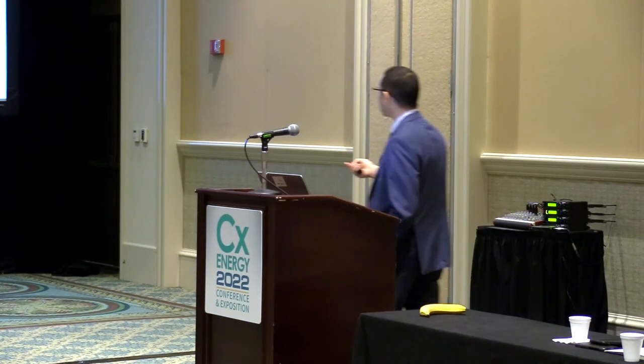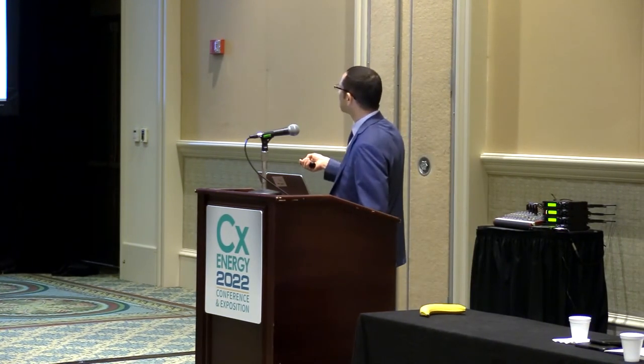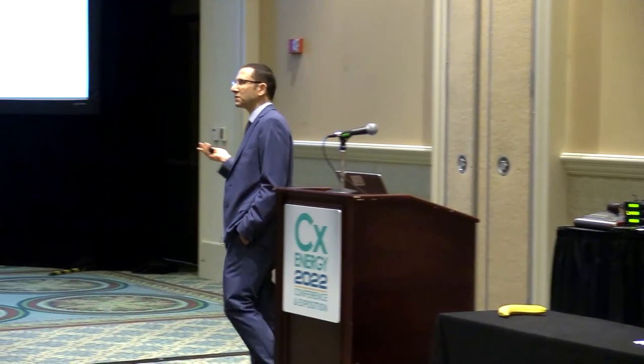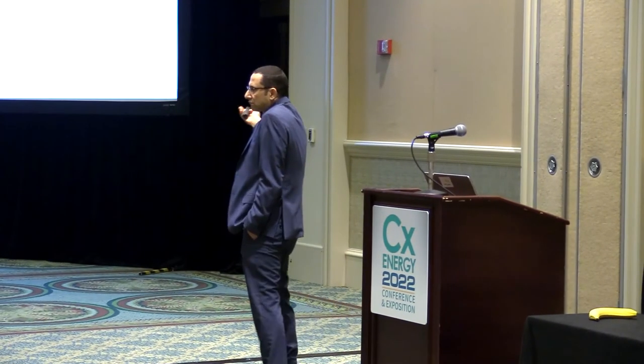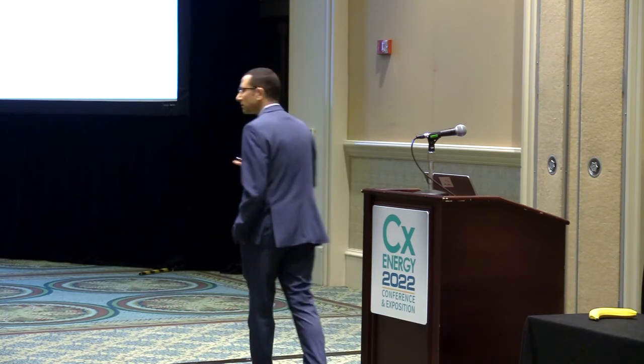In this example, air handler unit static pressure, as can be seen here, is not being met while the VFD is at 100%. Basically, the control vendor is doing everything he's supposed to do. He says, I can't meet static, I drove my fan to 100%, I can't do anything more for you, client. Sorry, go talk to your engineer.